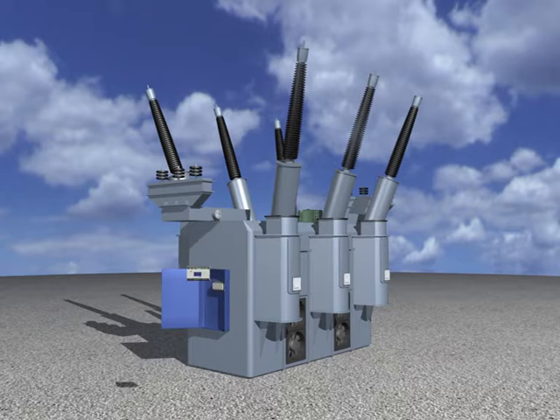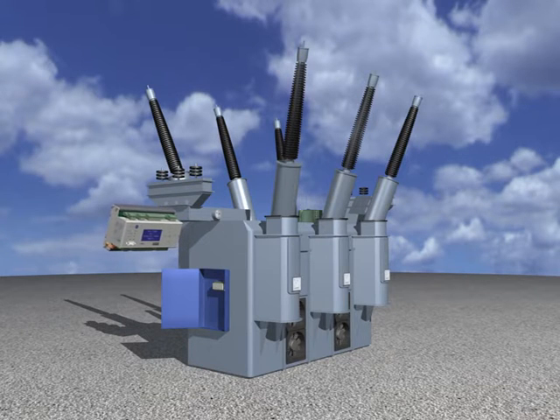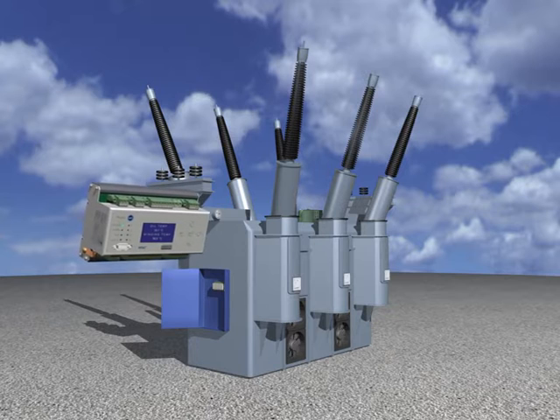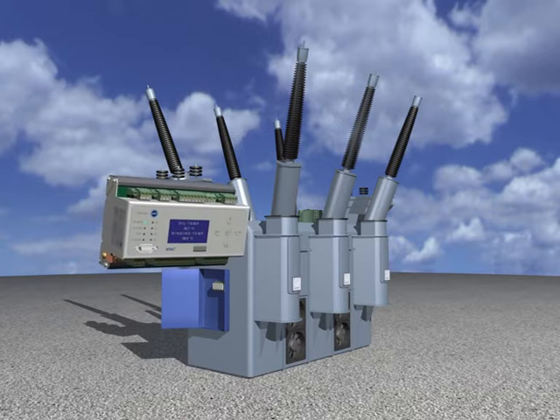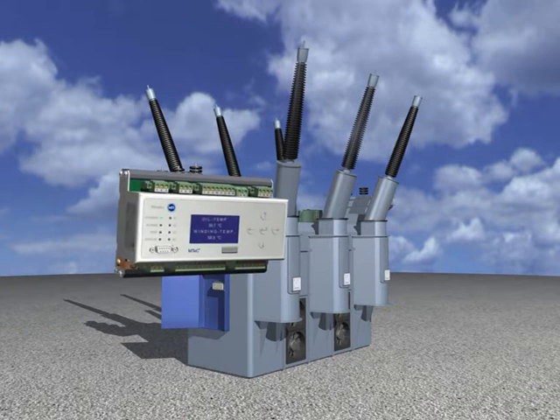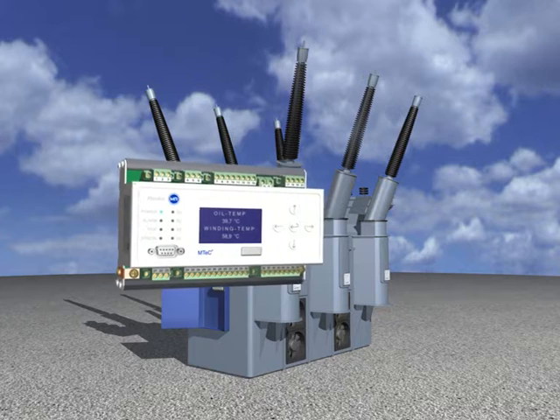This ability can be increased by using temperature monitoring devices with communication capabilities and converting the device from a single monitoring relay to a temperature management tool. The ideal winding temperature indicator will precisely reflect the behavior of the windings of a transformer, immediately indicate the highest temperature under all load conditions, and initiate appropriate cooling measures.